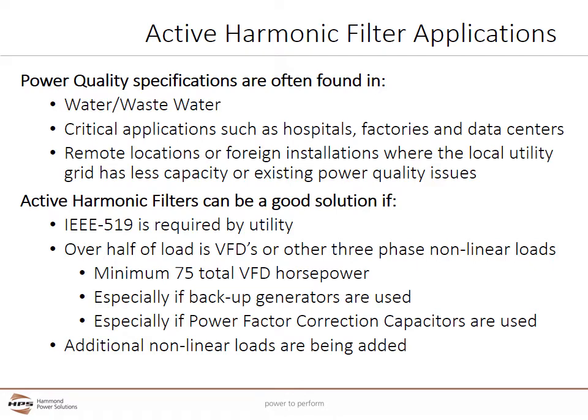Power quality specifications are often found in water and wastewater installations, as well as critical applications such as hospitals, factories, and data centers, which have many three-phase nonlinear loads that need to be corrected. Active harmonic filters are often deployed in remote locations or foreign installations where the local utility grid has less capacity or existing power quality issues — for example, an oil field with multiple wells in a rural location with a power grid never designed to supply such large three-phase loads. Active harmonic filters can be a good solution if IEEE 519 is required by the utility, and most utilities now monitor for IEEE 519 compliance.